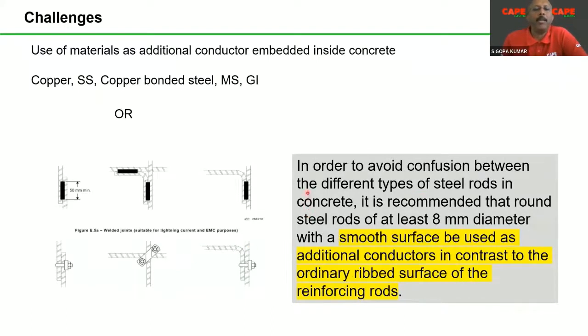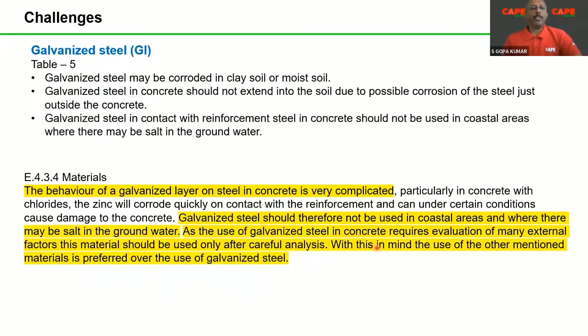But the standard also has a recommendation. In order to avoid confusion between different types of steel rod in concrete, it is recommended that a round steel rod of at least 8 mm diameter with a smooth surface be used as an additional conductor, in contrast to the ordinary ribbed surface of the reinforcing rod. Please read it: it is recommended. If in a standard the word recommended is used, that means the standard is recommending it. You can use the rebar, but the standard is recommending a conductor with a smooth surface, that means a conductor of copper, stainless steel, or whatever the material, with a smooth surface as an additional conductor in the concrete, which is preferred more than the ribbed material.